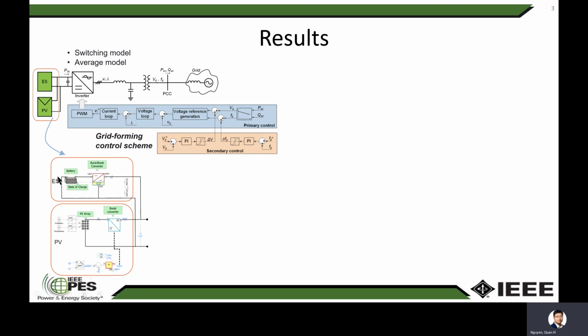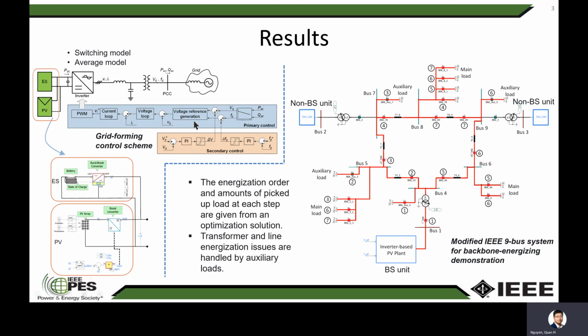And here are the models of energy storage and PV. For the energy storage, we have to use a buck boost converter for the bidirectional power flow. For PV, we only need to use a boost converter to boost the voltage here to a higher voltage here and apply this voltage to the inverter. For the inverter, we were able to test both the switching model and average model. And then we applied this grid forming control to this black start unit in an IEEE nine-bus system.